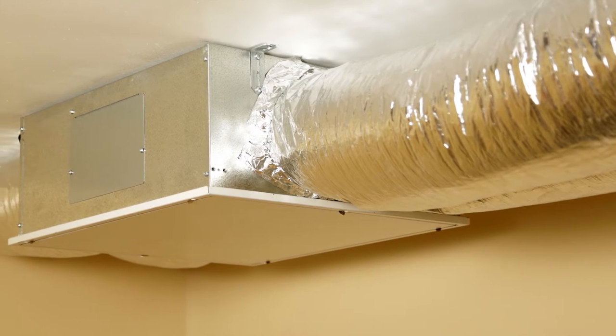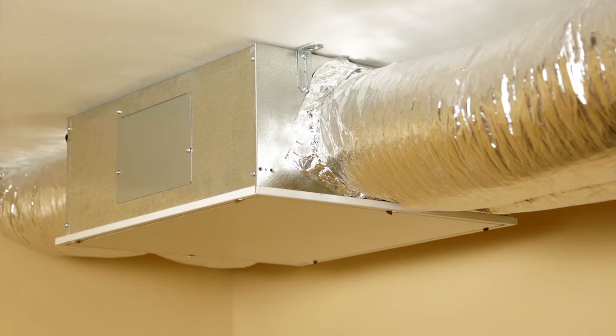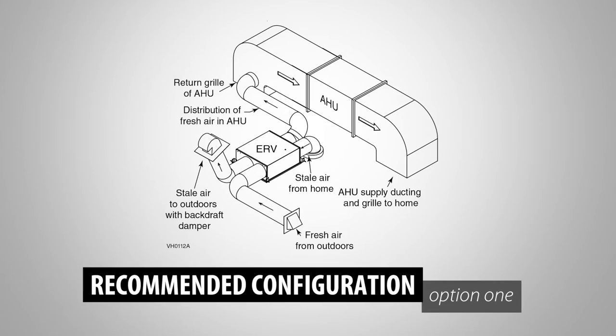There are two ways to integrate the ERVS-100 with the air handling unit. The recommended configuration distributes fresh air from the ERVS-100 into the air return of the AHU. In this configuration, the connection should be made as close as possible to one of the AHU return grills to ensure proper functioning of the built-in fresh air damper. In this configuration, you likely will want to install the stale air exhaust registers in a bathroom, kitchen, or living room.